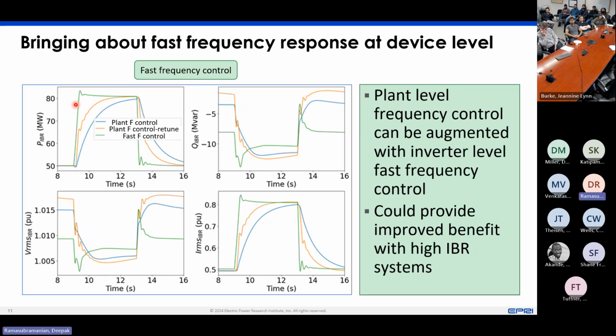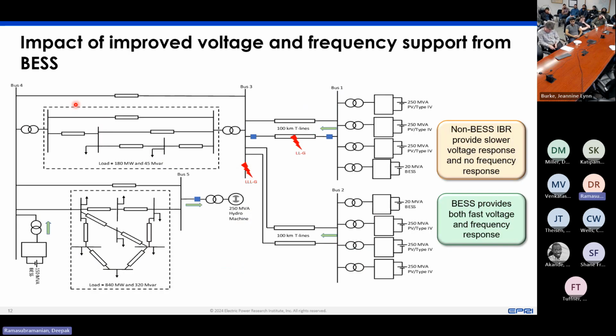So utilizing this fast voltage and fast frequency response at the device level, what kind of impact would it have on the grid? We tested that out on a few different networks. Let's walk through that. We tested that out on a microcosm system that can be representative of a lot of transmission networks that we see. We see renewable energy zones where you have clusters of inverter-based resources connected to the rest of the network through long transmission lines. There are some load centers, and then there are a few more resources connected all over. And because we didn't want to look at a 100% inverter system, we wanted to see a 100% renewable system, we added a hydro machine.